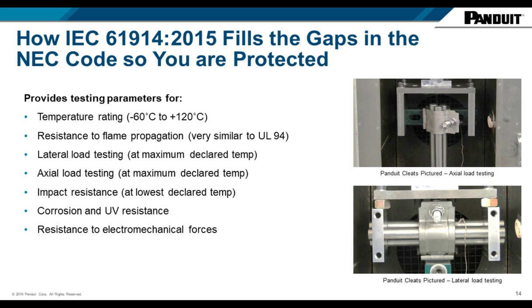We perform impact resistance testing at the lowest declared temperature — important for polymer cleats whose properties change dramatically at minus 40°C. We drop a known weight from a known height onto the weakest part of the cleat to check for fracture. We test against accelerated weathering, looking at corrosion and UV resistance, and we also test the electromechanical forces.